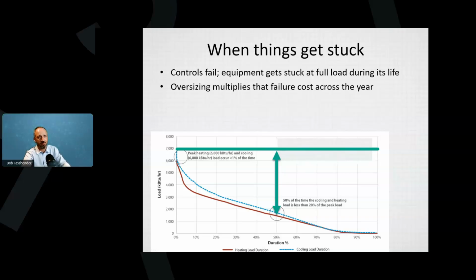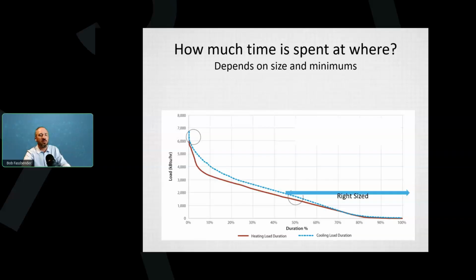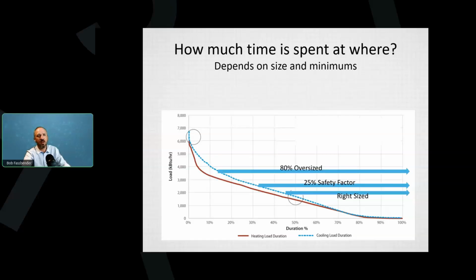Okay, that's just an example of what happens. It makes the energy calculation really easy though. So how much time is spent where if things are working as they should be? So if we have a right size building and it's just on 24/7, just for simplicity, you'll see that it's at its minimum over 50% of the time. And the rest of the time it's above its minimum. If you have a 25% safety factor, you're looking at being at the minimum almost 70% of the time. So it's almost a constant volume system at that point. 80% oversized, depending on if you're doing this by heating or cooling, you're at minimum 90% of the time.